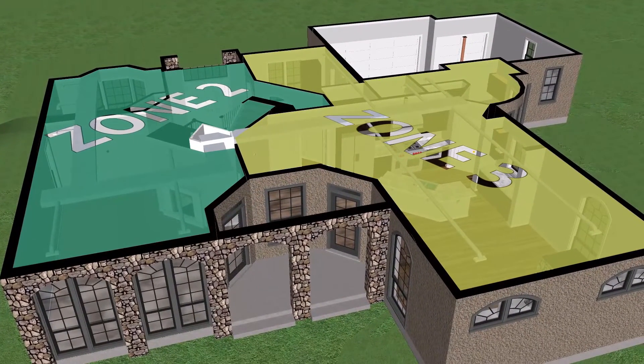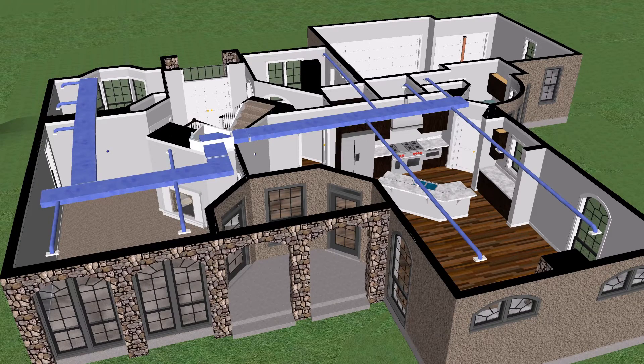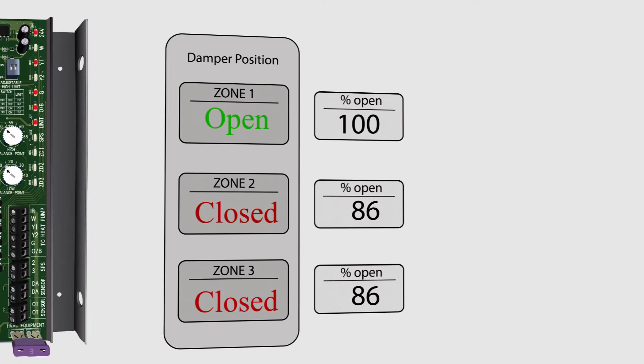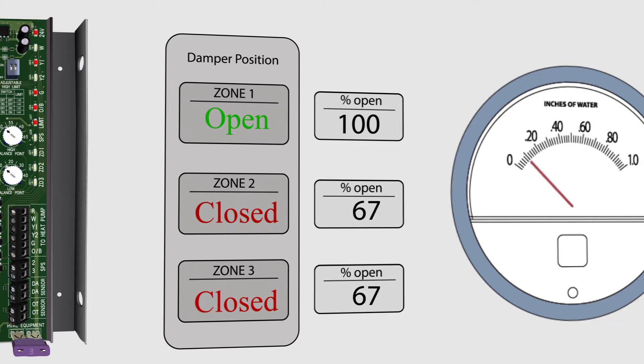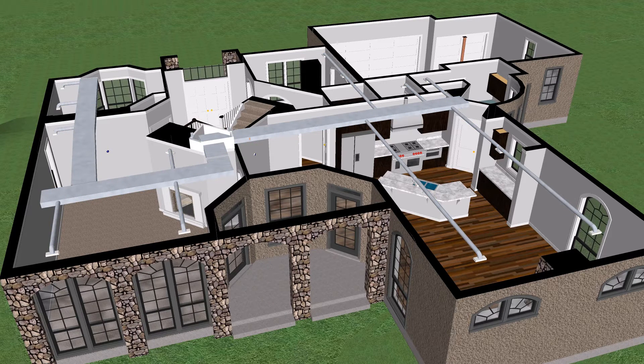And we zone off three zones — three sections of that house. And we have electronic zone dampers, not to be misconstrued with bypass dampers. Electronic zone dampers are designed to open or close the air entering into a zone being controlled by a thermostat, which goes back to a zone control panel. A zoned home forced air heating and air conditioning needs to have bypass.